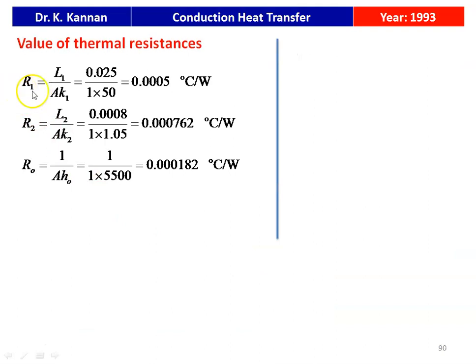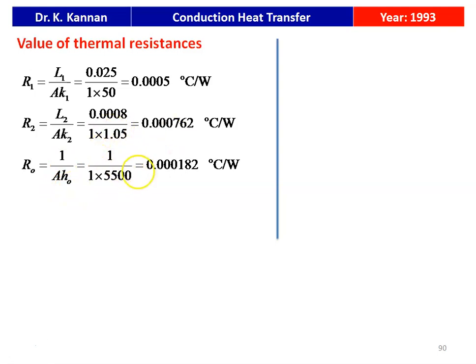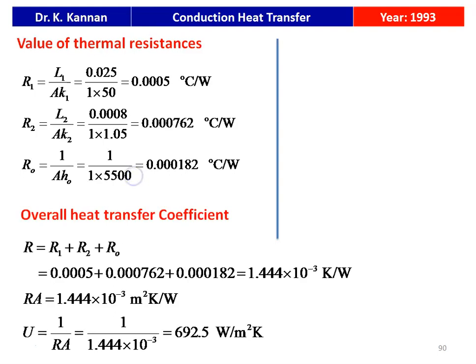Calculating resistances with area = 1 m². Resistance due to cast iron: R1 = L1/(A·K1) = 0.025/(1×50) = 0.0005°C/W. Resistance due to enamel: R2 = L2/(A·K2) = 0.0008/(1×1.05) = 0.000762°C/W. Convection resistance: Ro = 1/(A·Ho) = 1/(1×5500) = 0.000182°C/W. Total resistance R = R1+R2+Ro = 1.444×10⁻³ K/W. Area-weighted resistance RA = 1.444×10⁻³ m²·K/W.